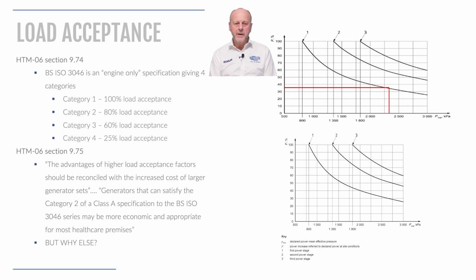The standard acknowledges that there is a difference in engine performance, and so it makes it dependent on the brake mean effective pressure that the engine is able to deliver. If you like, the amount of torque the engine can deliver into the shaft and hence make available to the alternator. The HTM guidance considers the engine standard, which is BS ISO 3046, which is front and center when it comes to load acceptance, setting out the various performance categories as set in the engine standard and not the generating standard, as we can see shown on the slide.